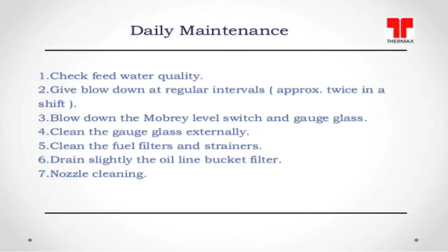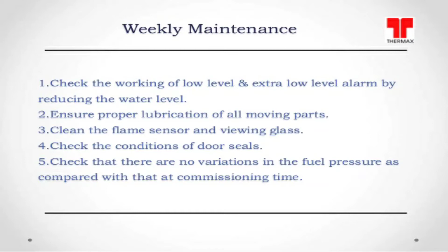First, check the working of low level and extra low level alarm by reducing the water level. Second, ensure proper lubrication of all moving parts. Third, clean the flame sensor and viewing glasses. Fourth, check the condition of door seals. Fifth, check that there is no variation in the fuel pressure as compared with that at commissioning time.